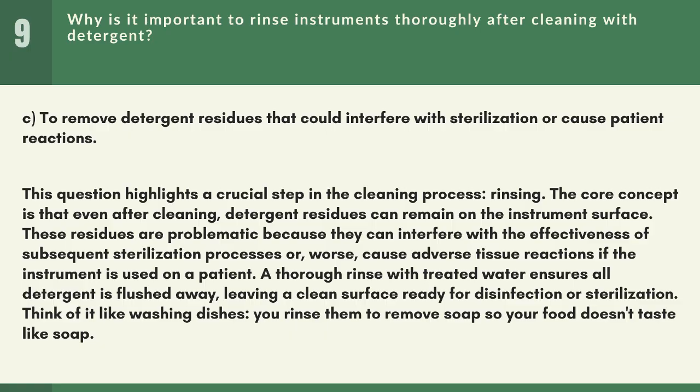This question highlights a crucial step in the cleaning process: rinsing. The core concept is that even after cleaning, detergent residues can remain on the instrument surface. These residues are problematic because they can interfere with the effectiveness of subsequent sterilization processes or, worse, cause adverse tissue reactions if the instrument is used on a patient. A thorough rinse with treated water ensures all detergent is flushed away, leaving a clean surface ready for disinfection or sterilization. Think of it like washing dishes. You rinse them to remove soap so your food doesn't taste like soap.